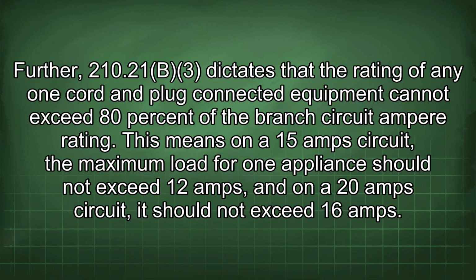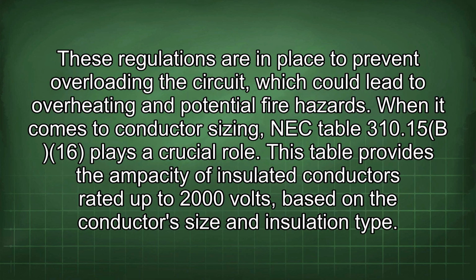Further, 210.21(B)(3) dictates that the rating of any one cord and plug connected equipment cannot exceed 80% of the branch circuit ampere rating. This means on a 15 amps circuit, the maximum load for one appliance should not exceed 12 amps, and on a 20 amps circuit, it should not exceed 16 amps. These regulations are in place to prevent overloading the circuit, which could lead to overheating and potential fire hazards.